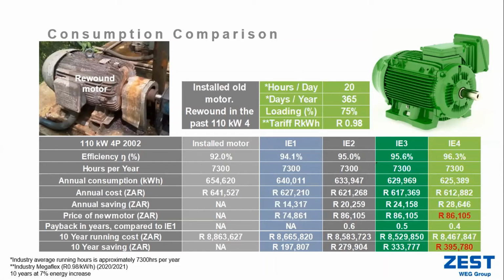And then we calculated, based on efficiency and the power absorbed, what our annual consumption per year is. And as you can see, even just going from the old motor to a new IE1 standard efficiency motor, we can already see there's a benefit in energy consumption. In other words, less energy is consumed because of the newer motor with newer designs. There's already a saving. Then we worked out what you would pay for that motor. Okay, that would be my annual cost. There's no savings. There's no price of a new motor. There will be no payback. And we said that's what it will cost to run that motor for 10 years.